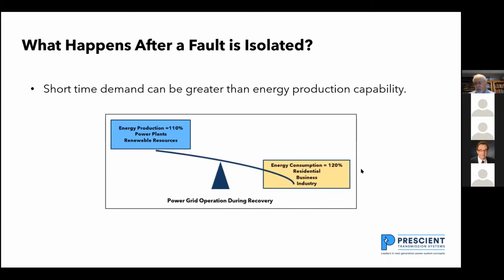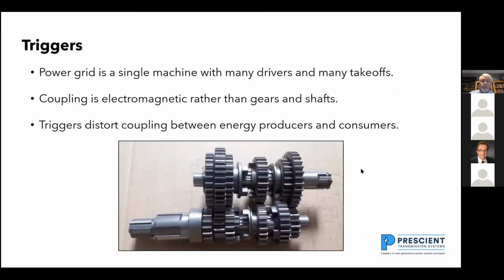So I've got the system running under normal configuration. I have a transient, a fault that lasts 100 milliseconds, and then I clear the fault. And when I clear the fault, the energy production could be 110% of what it was before the fault occurred, but the energy consumption could be 120%. So I've got a mismatch during recovery of production and consumption. And the reason why we're concerned about triggers is we think of the electrical system as being a single machine.